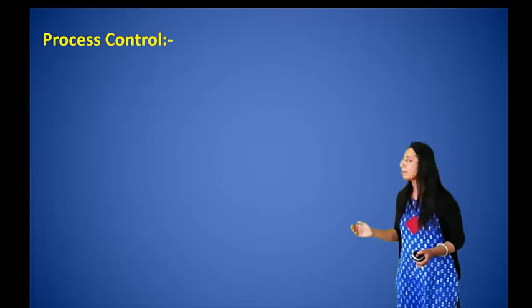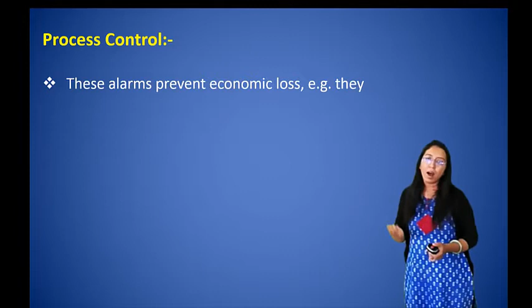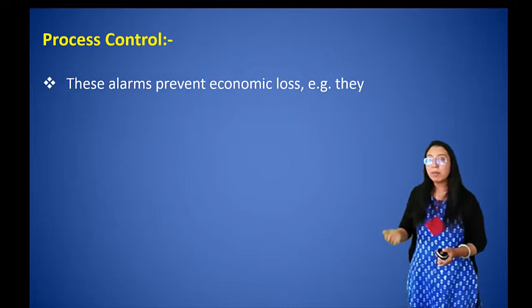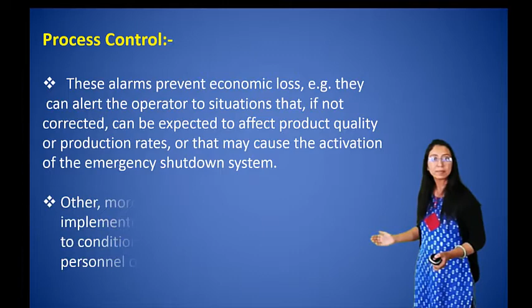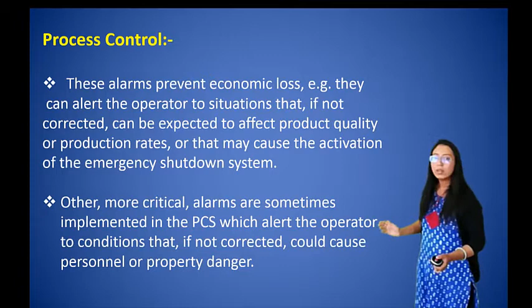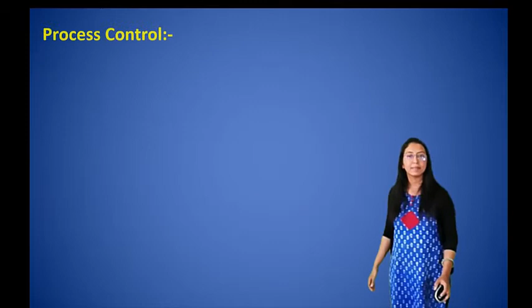These alarms prevent economic loss. So next we have talked about how to get information through the alarm system if an emergency occurs. Here they can alert the operator to a situation that, if not corrected, can be expected to affect product quality or production rates, or that may cause the activation of the emergency shutdown system. If any fault occurs, then we can get information through the alarm system. Other more critical alarms are sometimes implemented in the process control system, which alert the operator to a condition that, if not corrected, could cause personnel or property danger.